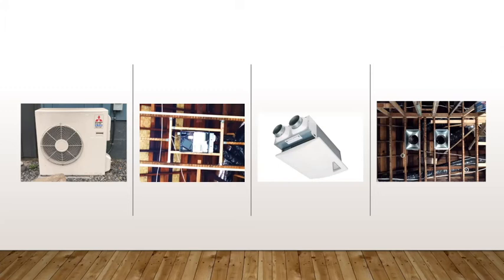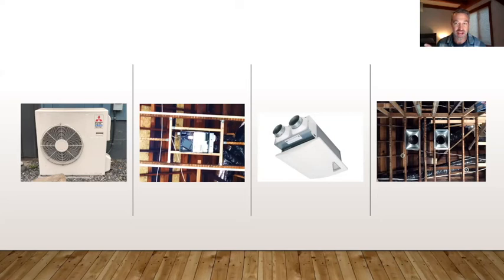Okay, thanks. And that's kind of the problem you have when you use a mini split heat pump system and you use those head units or those cassette units. One of those units can handle a large area, 600 square feet or so. So in a modern open floor plan house, you don't need very many head units because it's all open floor plan. If you have a new second story that you're adding to a house and it's all bedrooms with closed doors, then you need to put a head unit in every single room because you don't get that airflow once the door's closed. And so that's why I like the ducted heat pump system in that scenario.